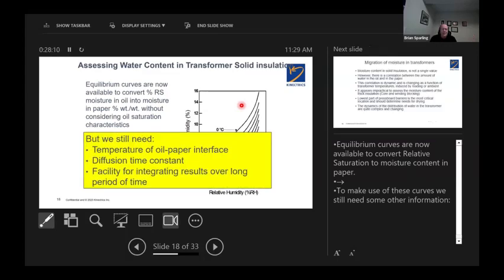So we now know we need the temperature of the oil-paper interface, and that implies the winding hotspot temperature. The diffusion time constant, we have the table. And the facility of integrating results over a long period of time, which is possible now with online monitoring of transformers.